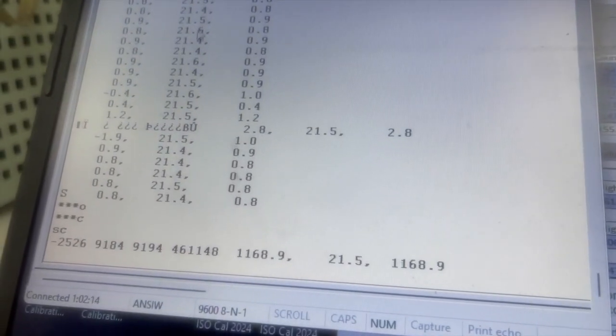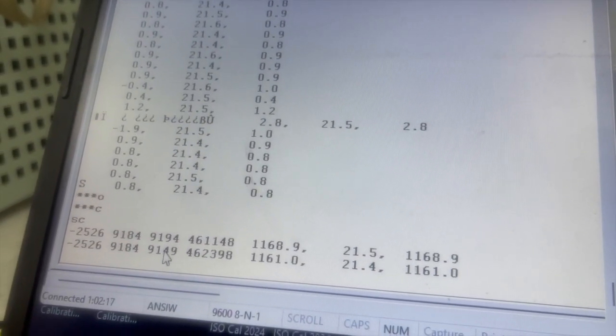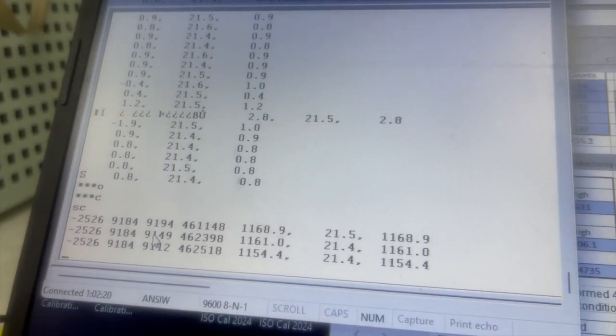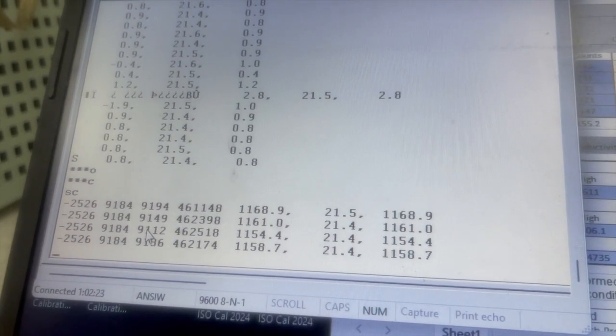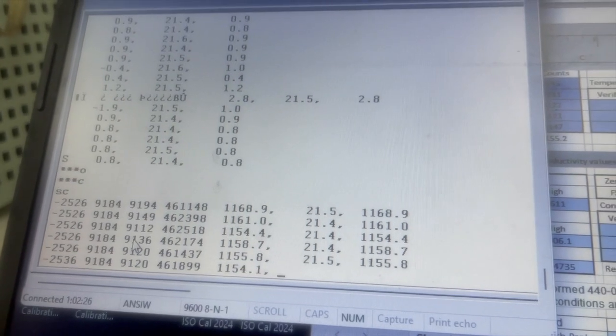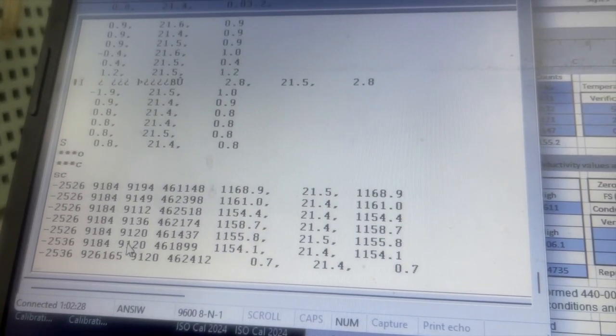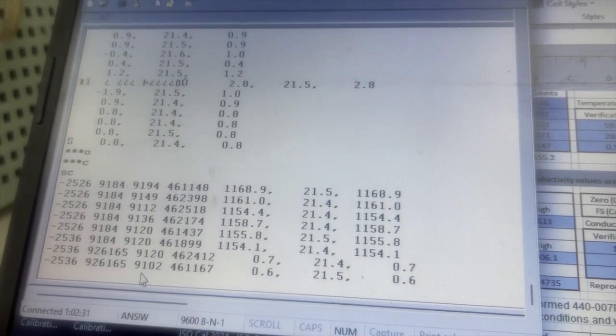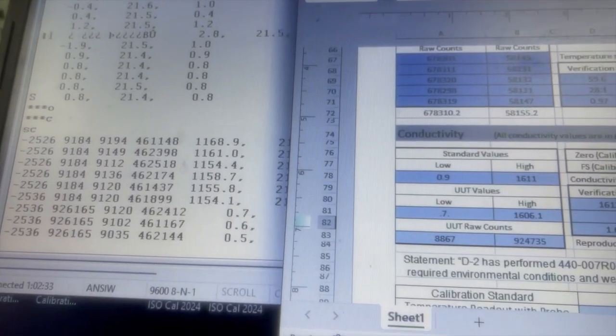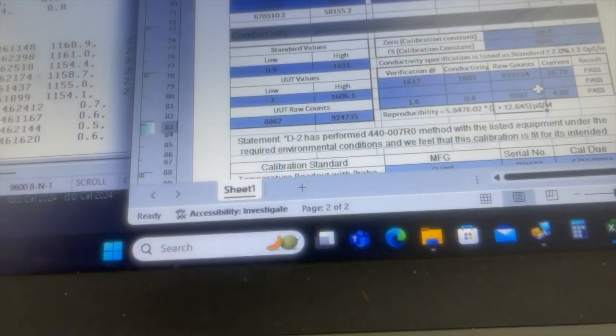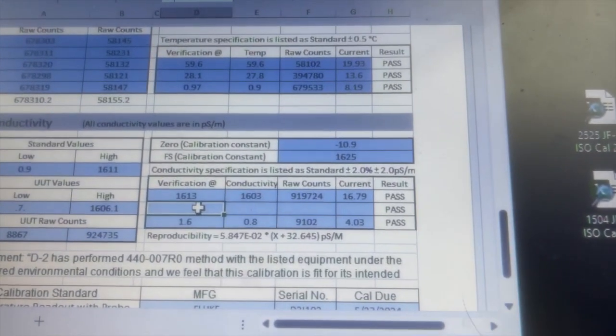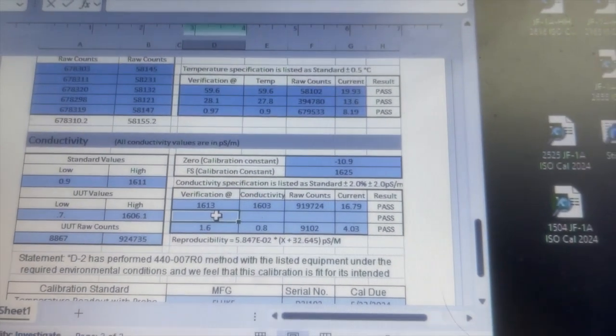And now we have to get the sensor counts. So we go into cal mode, and the sensor counts are 9194, but you have to wait for it to adjust. Hold on. 9102, which is fine. It's all a pass. Now we just have to get the middle value to verify.